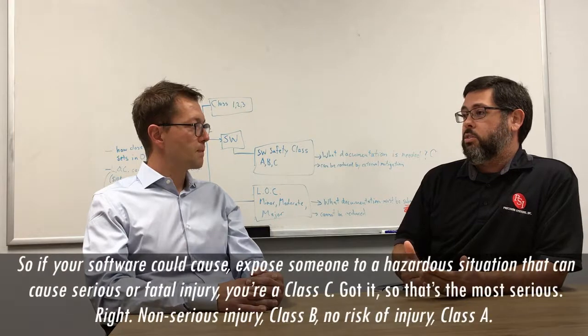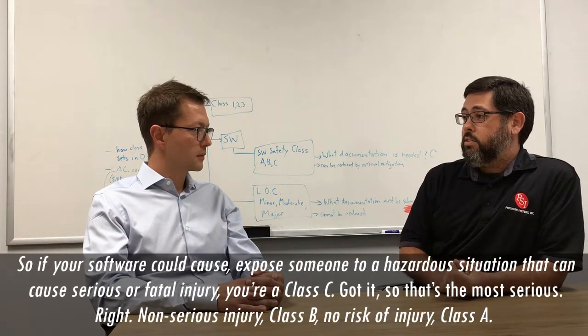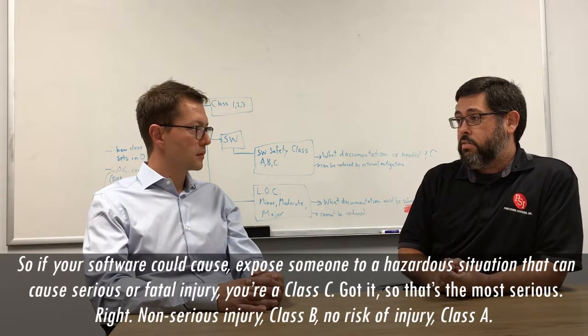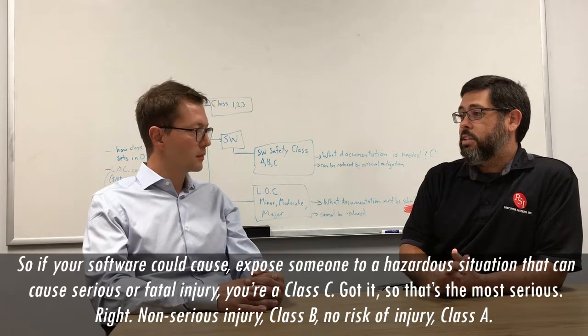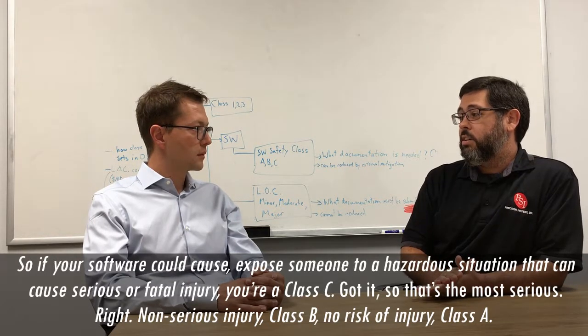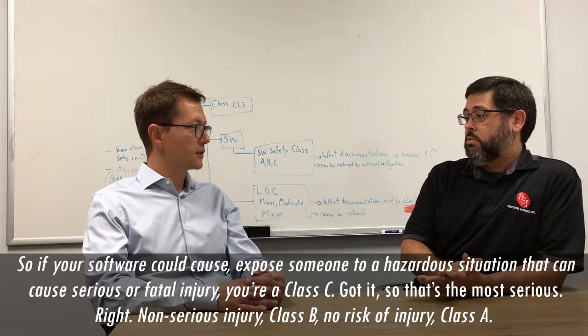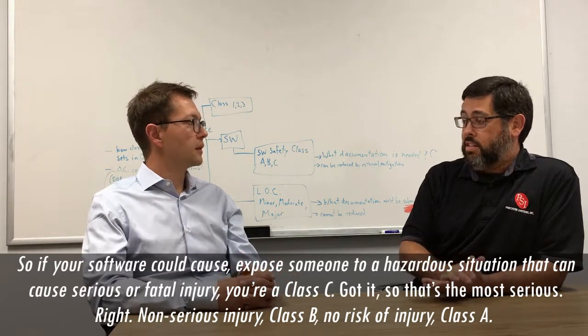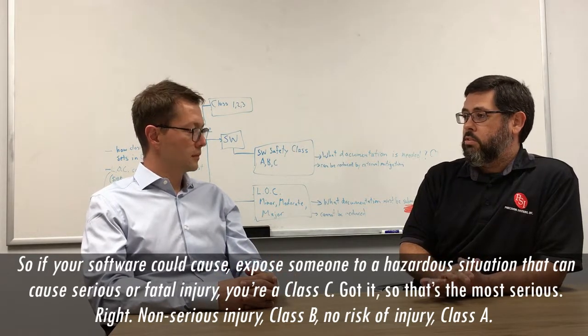So if your software could expose someone to a hazardous situation that could cause serious or fatal injury, you're Class C. Got it. So that's the most serious. Right, most serious. Non-serious injury, Class B. No risk of injury, Class A.